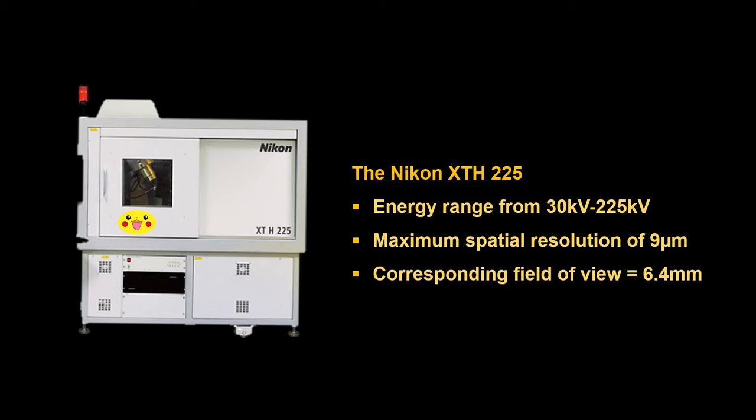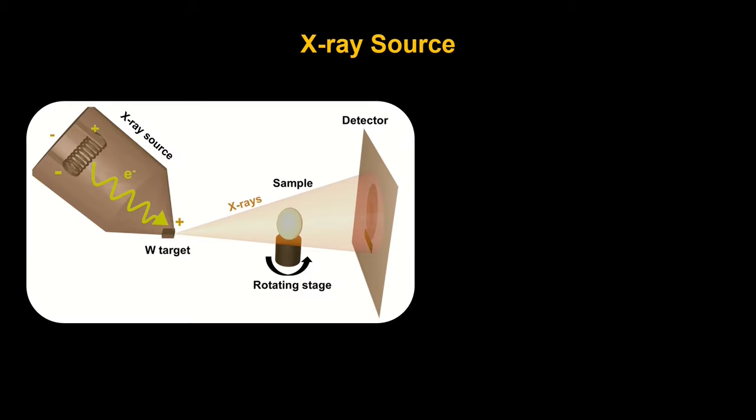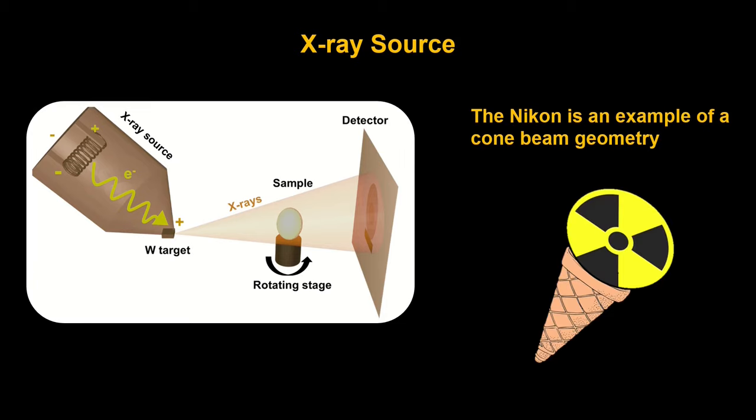If we strip the Nikon down to its core parts, we would be left with these three essential components. You've got the X-ray source, you've got the detector, and you've got the sample on a rotating stage in between them. We've talked about the X-ray source a bit in the last lecture on the basics of X-rays. The Nikon is an example of cone beam geometry. This is a natural geometry for a divergent beam. You have the X-rays produced at that tungsten target, and then they are emitting out at various angles towards the sample.